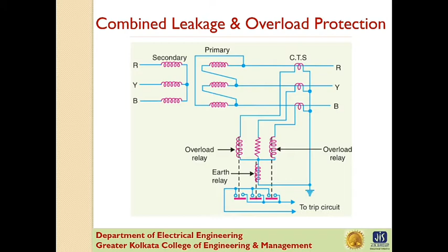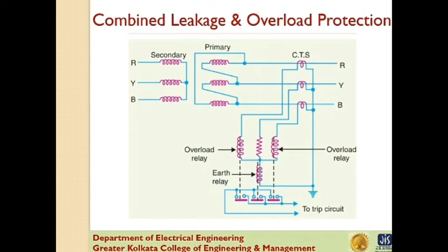This figure shows the schematic arrangement of combined leakage and overload protection in this system. Two overload relays and one leakage or earth relay are connected as you can see in the figure. The two overload relays are sufficient to protect against phase-to-phase fault. The trip contacts of the overload relays and the earth fault relay are connected in parallel. Therefore, with energizing of either an overload relay or the earth relay, the circuit breaker will trip.